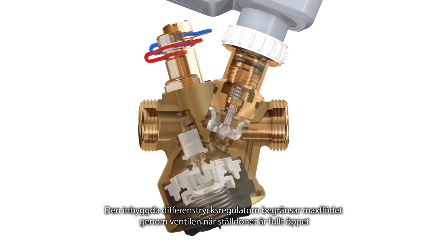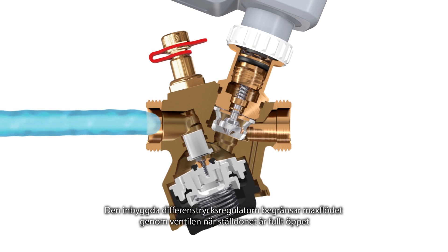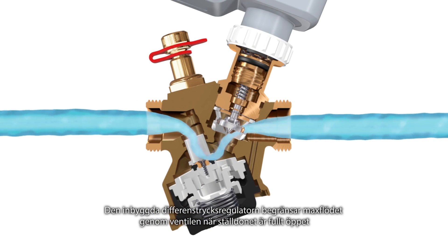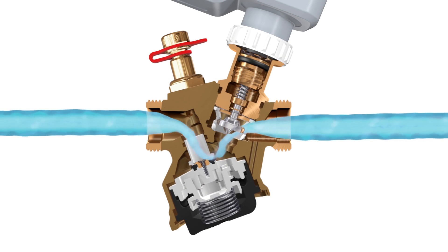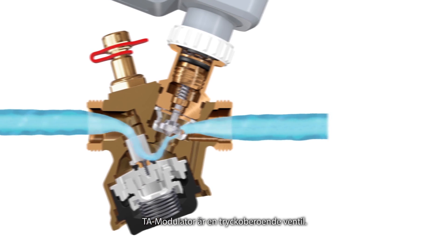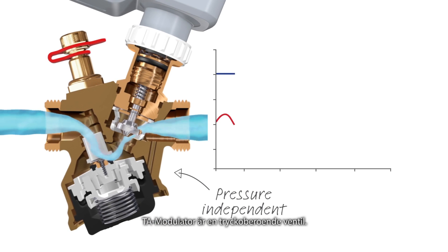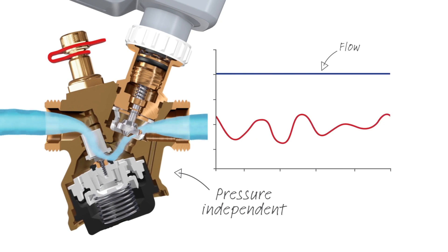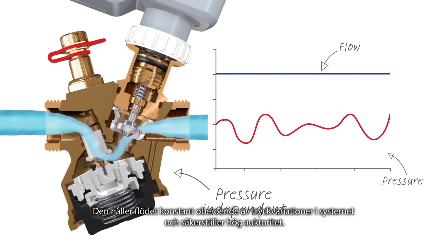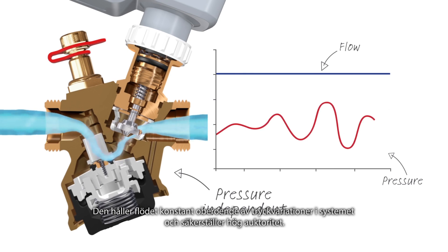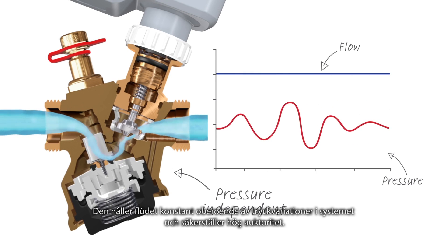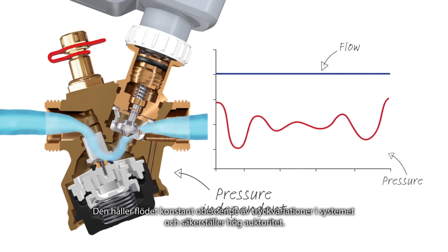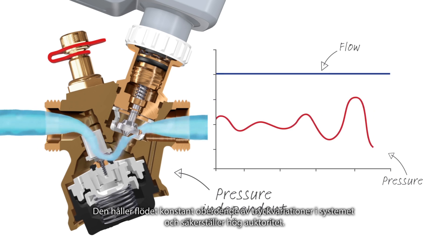The built-in pressure controller limits the maximal flow through the valve when the actuator is fully open. TA Modulator is a pressure independent valve — it keeps the flow constant regardless of pressure fluctuations in the system and guarantees high control authority.